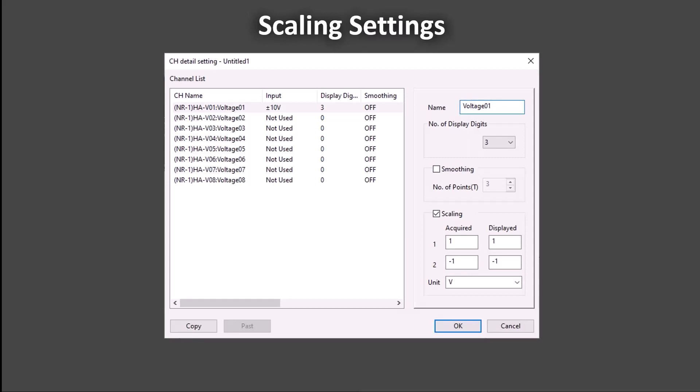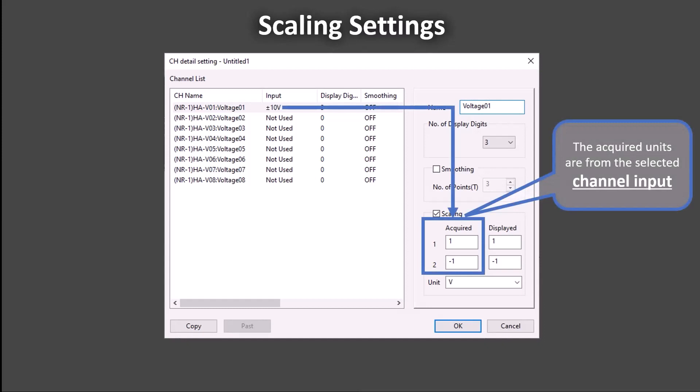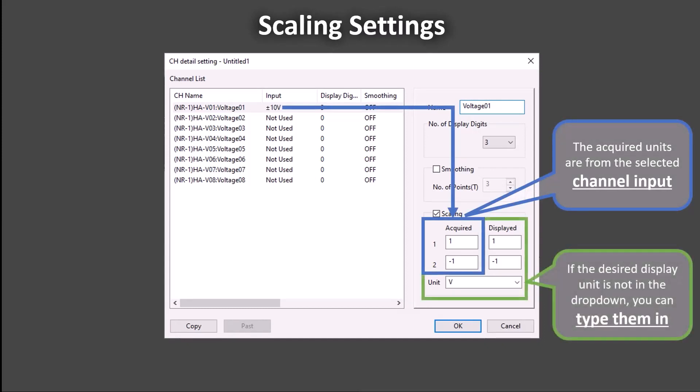The scaling is set by two acquired values scaled to displayed values. The units of measure used for the acquired values are set by the input channel. The units of measure for the displayed values are set manually in the unit box. The displayed units can be selected by dropdown or typed in manually.